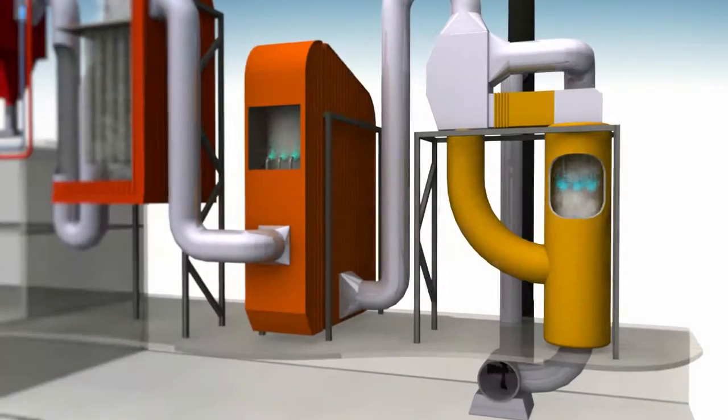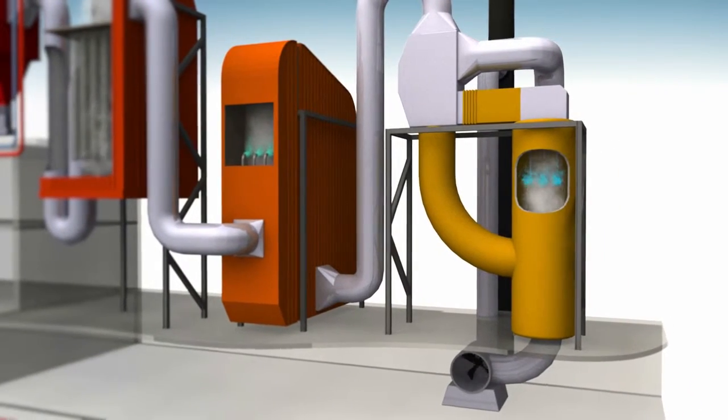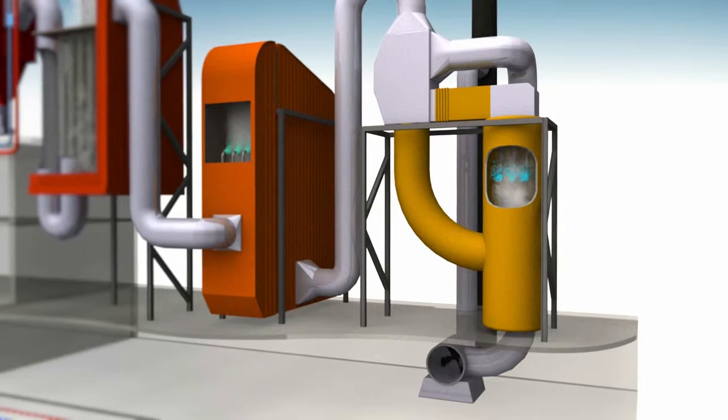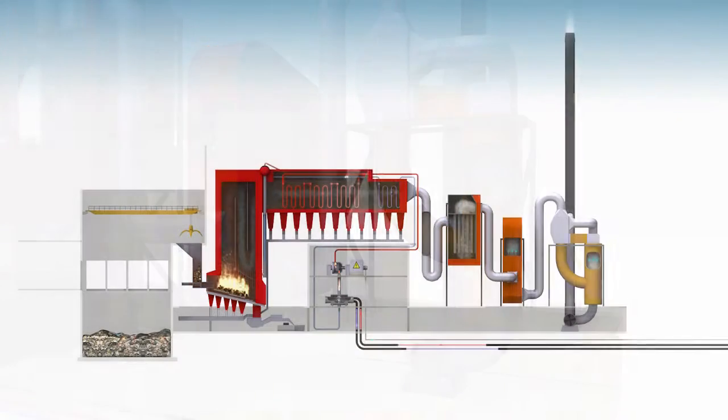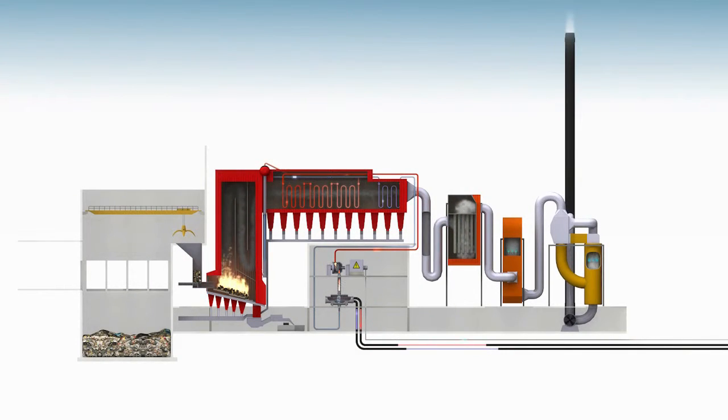The final stage of the cleaning process involves the use of what is known as a scrubber. In the scrubber, the flue gas passes through a mist of water. The scrubber removes chlorine and sulphur compounds, as well as any residual dust and heavy metals that may have escaped the bag filter. Finally, the treated flue gas is released into the atmosphere via a 75-metre tall chimney.